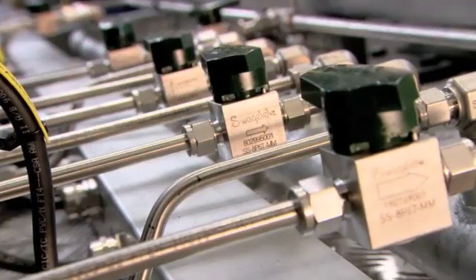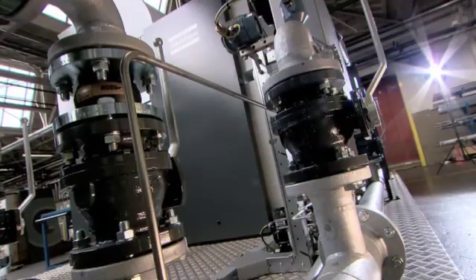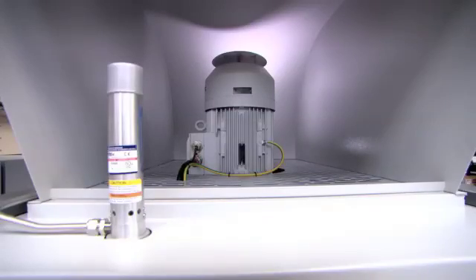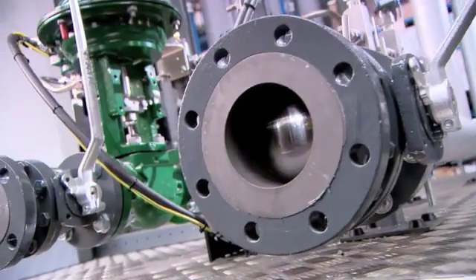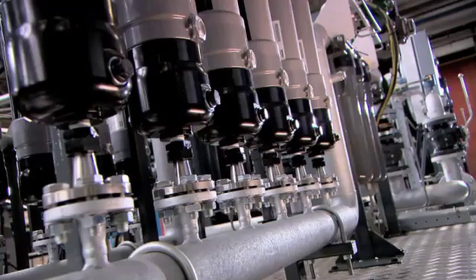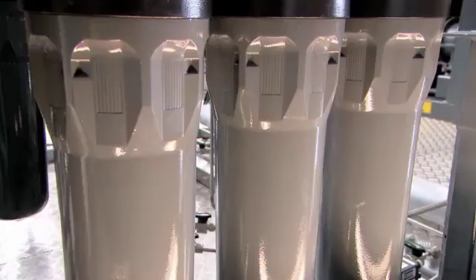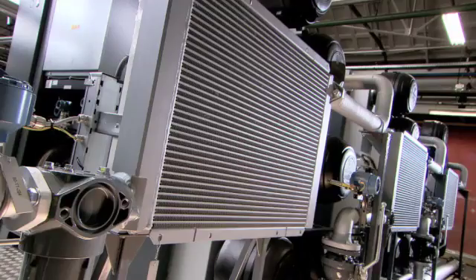Throughout the package, 150 pound flanged ball valves are used. Armoured and flame retardant cabling is routed through closed cable trays. Stainless steel tubing with electronic drains for condensate management was included. We included an IP55 fan motor with ducting and cubicle vortex cooler for increased reliability. The flanged common single point interface allows easy connection to the client's piping, minimising installation requirements on site. Special attention was given to the piping layout and material — 316 stainless steel or galvanised carbon steel — in order to minimise pressure drops while accessibility is optimised. Each dryer drain has its dedicated pre-filters to increase the quality of air going into the dryer, which prolongs the lifetime of the membrane dryers.